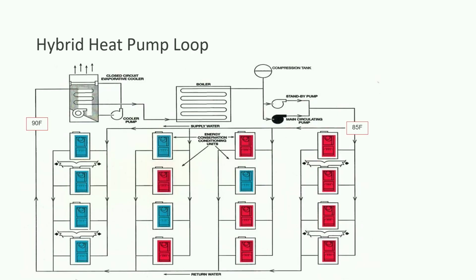This is the hybrid loop. So in this case, you're going to have a slightly higher temperature loop for a hybrid system. This is what we were talking about earlier with a hydronic coil. I can get some heating on a day like today with 80-degree water. So we run 80, 90-degree supply and return water temperatures, so it's a little bit higher water temperature, which you can get in a geothermal system. So that's something to consider from a hybrid heat pump and potentially a hybrid geothermal loop.